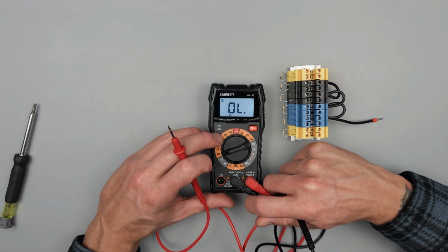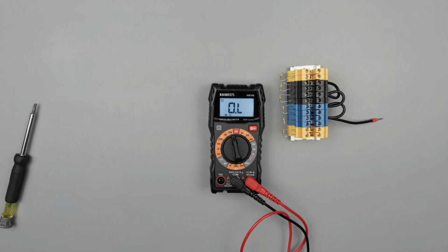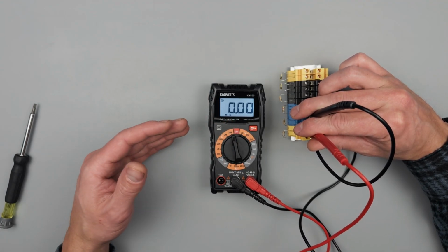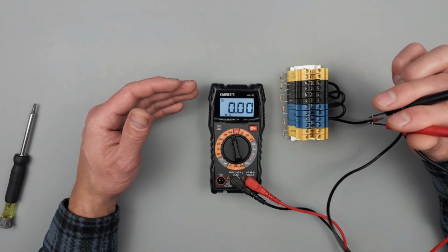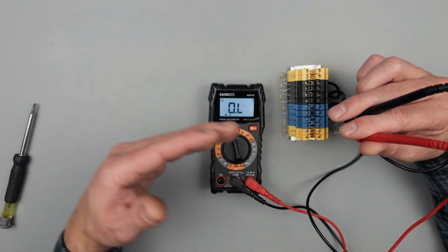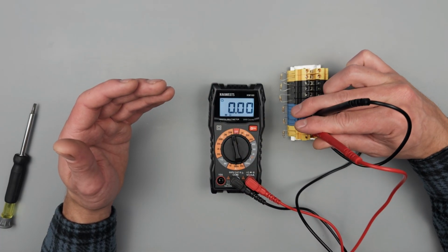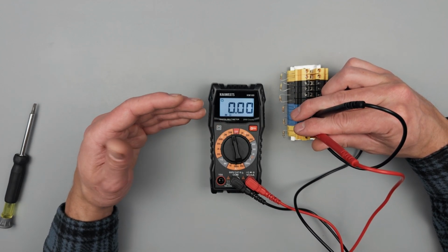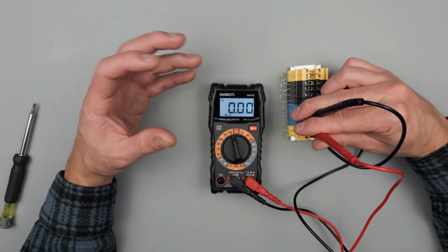For practice, we're going to start with the biggest value, and then we're going to try to figure out what's going on and what it says. So the first one, it just says zeros, but that actually tells us a lot of information. By saying nothing, it says a lot. If we had OL, that would mean that there's no continuity into the circuit. Something's open. It's an open circuit. But because we're getting all zeros, it's trying to say, hey, there's some level of resistance here, but it's too small for me to be able to read on this setting. Keep going down. Keep dialing it in.